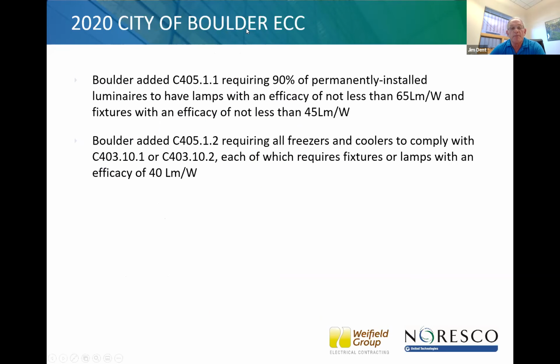Boulder added C405.1.1, which requires 90% of permanently installed luminaires to have lamps with an efficacy of not less than 65 lumens per watt and fixtures with an efficacy of not less than 45 lumens per watt. That requirement is exactly the same as the wording in the 2021 IECC. Denver just went with 65 lumens per watt for lamps and luminaires. So Denver's slightly different and a little more stringent.